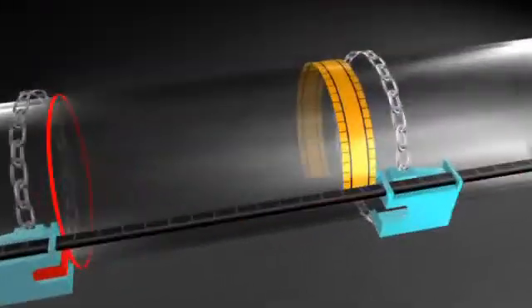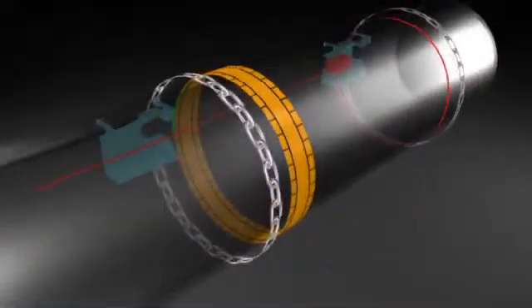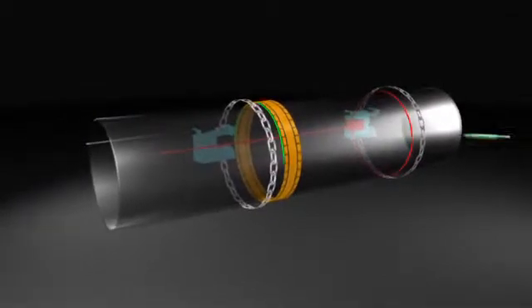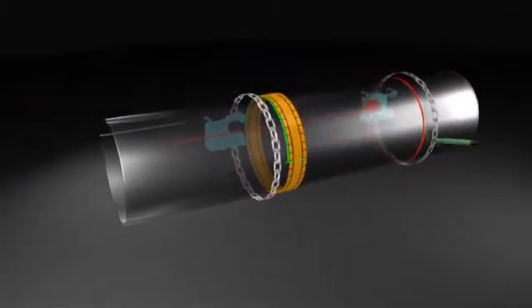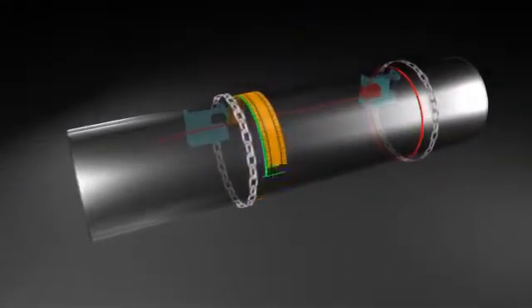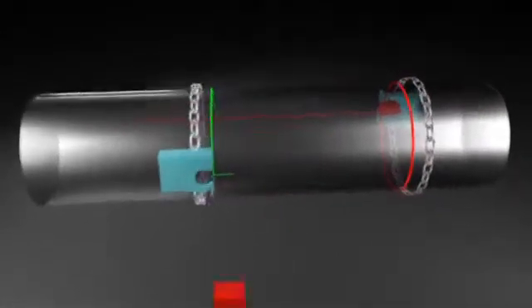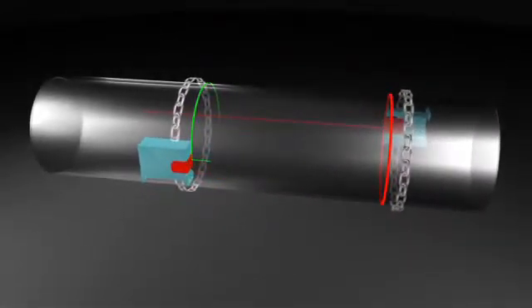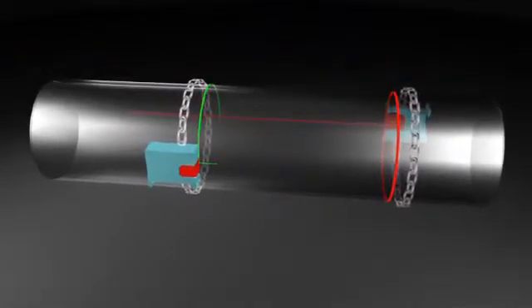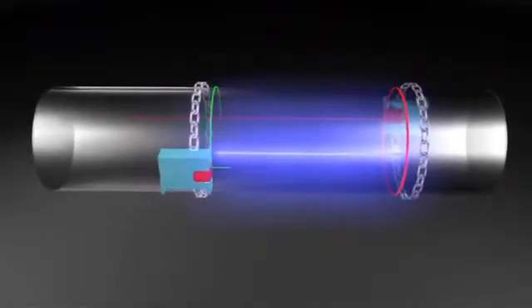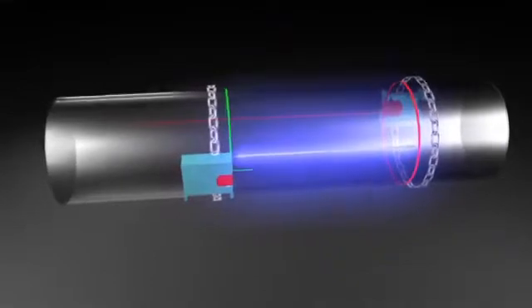Measure from line B to halfway around the pipe, keeping the chain and ruler straight. Draw a line halfway around the pipe and mark. Remove the ruler, slacken the chain and slip the guide rail around so the center of the rail is central to the mark. Tighten the chain and insert the other sensor. To check, measure the distance from the front of the second sensor to line A.